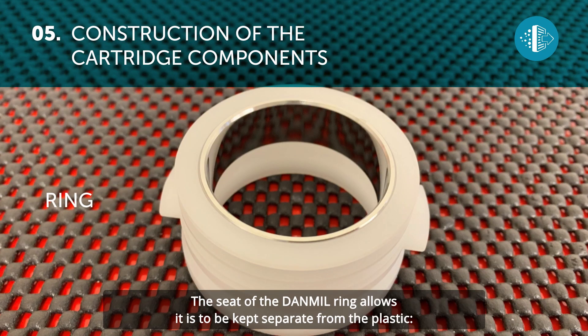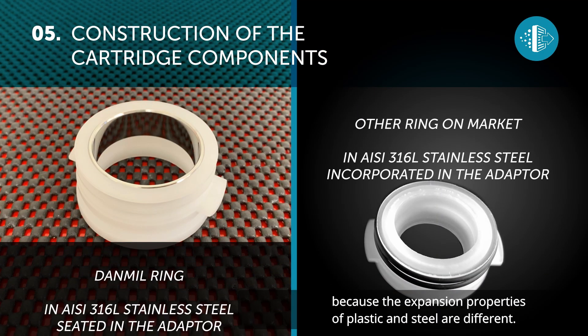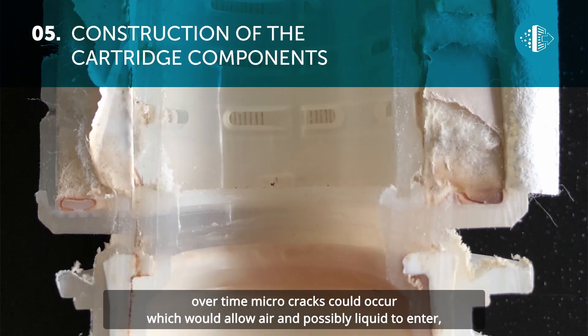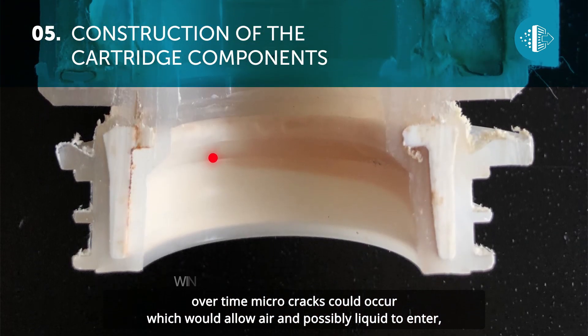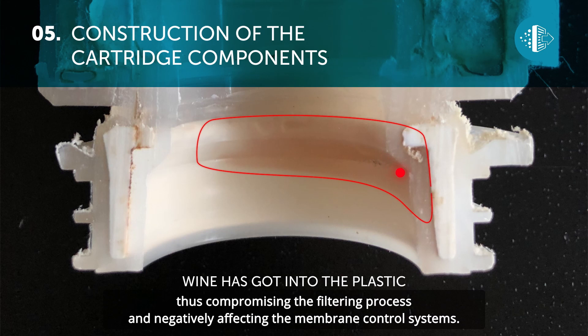The seal of the Danmil ring allows it to be kept separate from the plastic. This is an important technical feature because the expansion properties of plastic and steel are different. If the steel ring is inserted in the plastic of the adapter, over time micro cracks could occur which would allow air and possibly liquid to enter, thus compromising the filtering process and negatively affecting the membrane control systems.